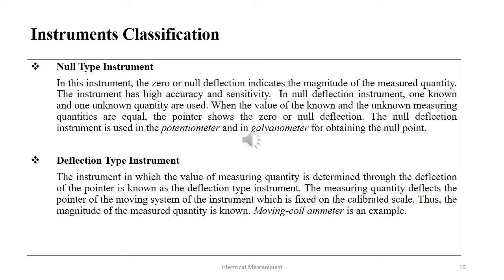The analog device is further classified into null type and deflection type. In the null type instrument, zero or null deflection indicates the magnitude of the measured quantity. This instrument has high accuracy and sensitivity. One known and one unknown quantity are used; when the values are equal, the pointer shows null deflection. The null deflection instrument is used in potentiometers and galvanometers for obtaining the null point. In the deflection type instrument, the value of the measuring quantity is determined through the deflection of the pointer on a calibrated scale. The moving coil ammeter is an example of a deflection type instrument.